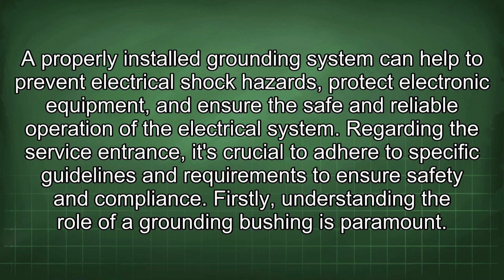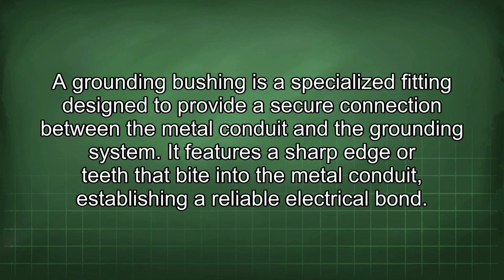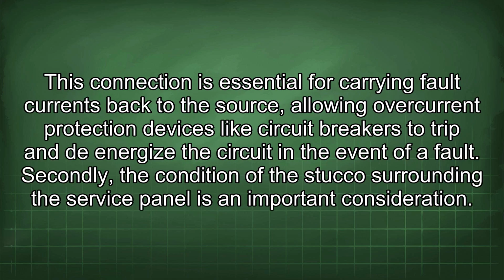Regarding the service entrance, it's crucial to adhere to specific guidelines and requirements to ensure safety and compliance. Firstly, understanding the role of a grounding bushing is paramount. A grounding bushing is a specialized fitting designed to provide a secure connection between the metal conduit and the grounding system. It features a sharp edge or teeth that bite into the metal conduit, establishing a reliable electrical bond. This connection is essential for carrying fault currents back to the source, allowing overcurrent protection devices like circuit breakers to trip and de-energize the circuit in the event of a fault.